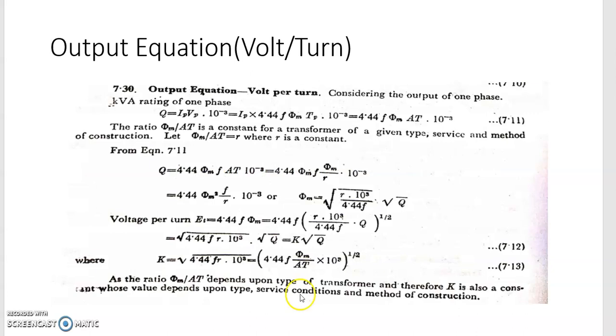Now, what to do with these output equations — you should also know how to calculate volt per turn, since you usually get numericals involving the output equation along with volt per turn of a given transformer. Considering the KVA output of one phase, the equation we have already derived shows that the ratio phi_M / AT is a constant for a transformer. The cross-sectional area and number of turns, once decided during design time, will not change with load current or flux. Let's name this constant as small r.